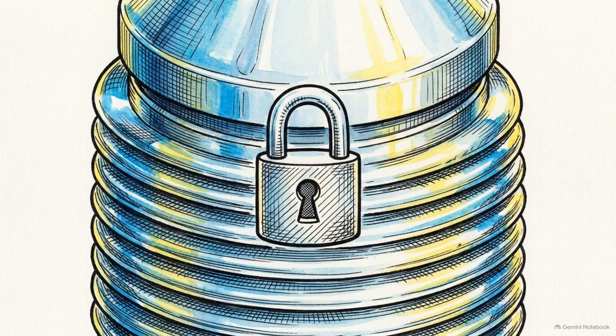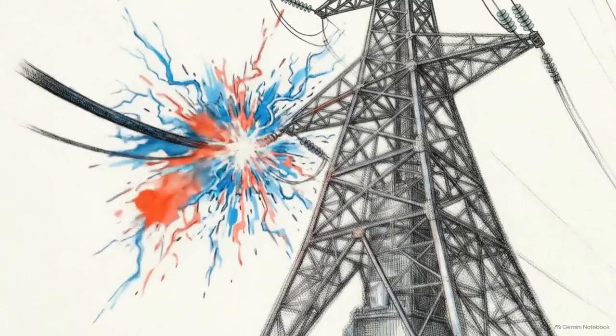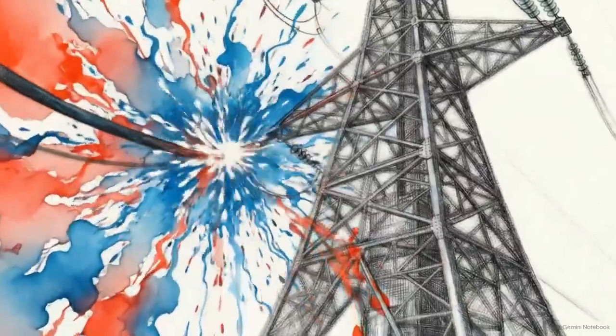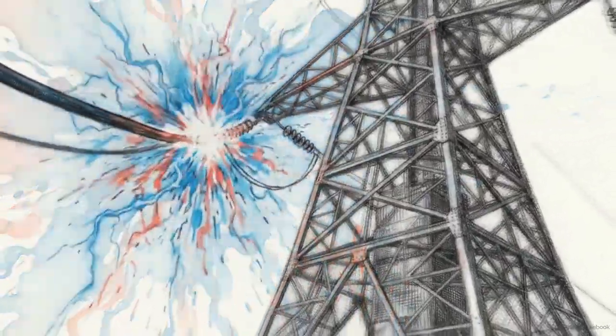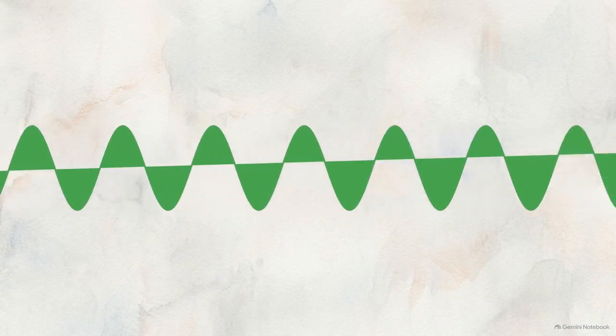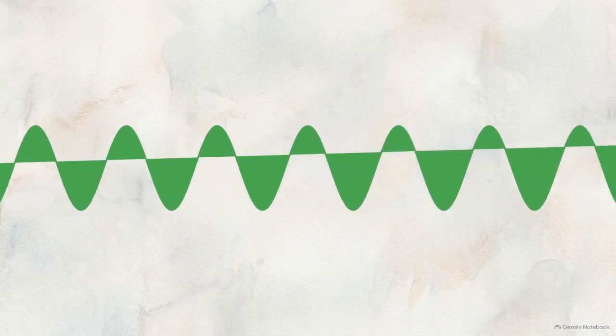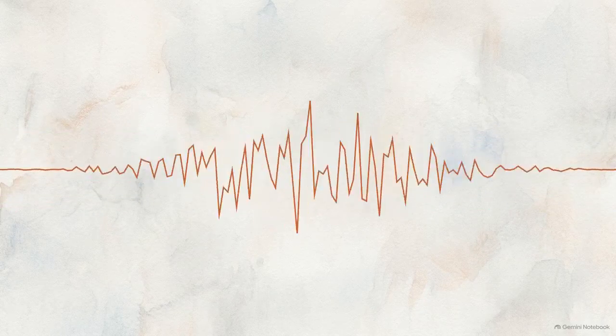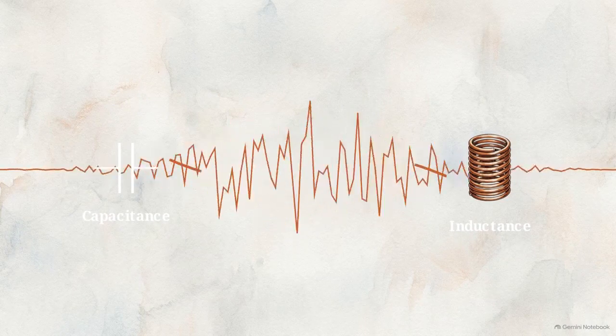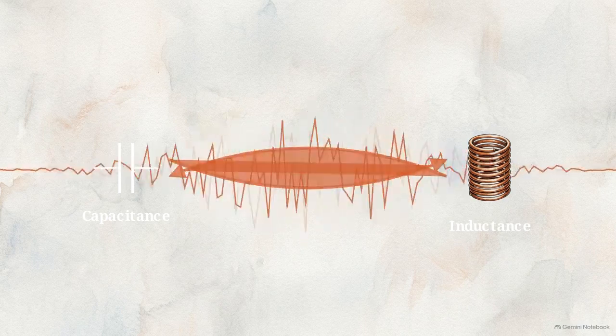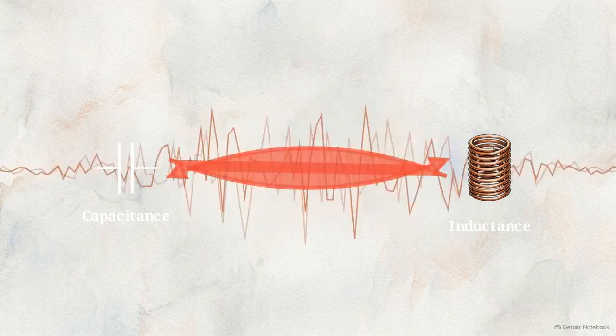Even with strict environmental sealing and phase correction, there is one condition that threatens to compromise the CVT: sudden grid faults. When line switching or short circuits occur, they can trigger an electrical phenomenon called ferroresonance, a sustained high-frequency oscillation of voltage. This is a volatile feedback loop triggered by the interaction between the capacitance inside the CVT tower and the nonlinear magnetic inductance of the grid during a transient event.